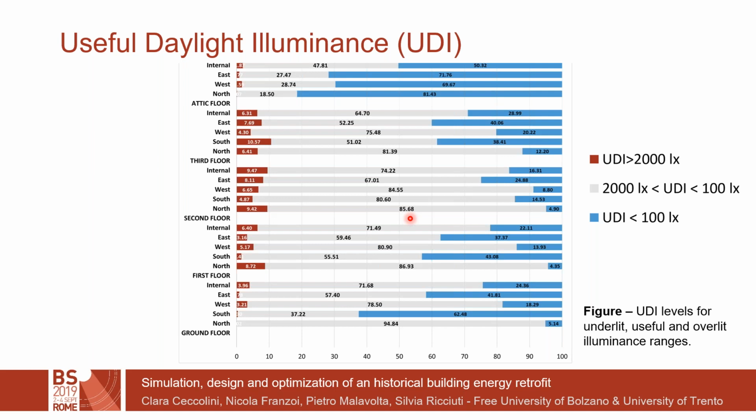As you can see in this figure, for a considerable amount of time, the illuminance level is below 100 luxes in many zones, and this reinforces what resulted from the static analysis. Therefore, we concluded that the use of sensors for integrating artificial lighting with daylight would be an unjustified cost, and rather we considered more important improving the energy efficiency of the lighting system.